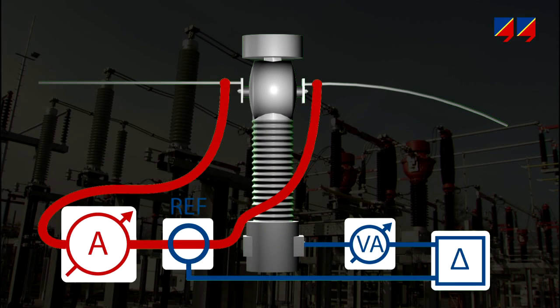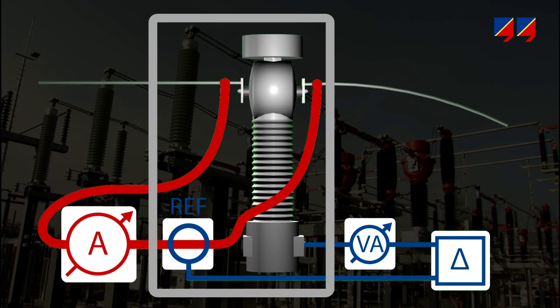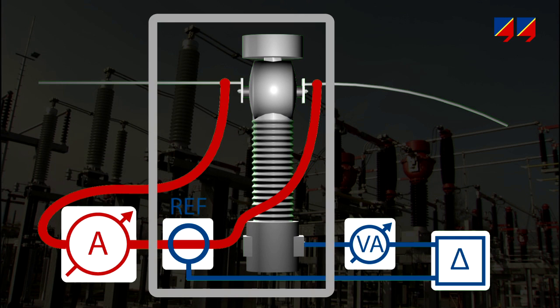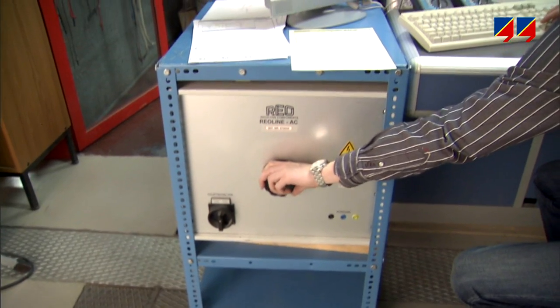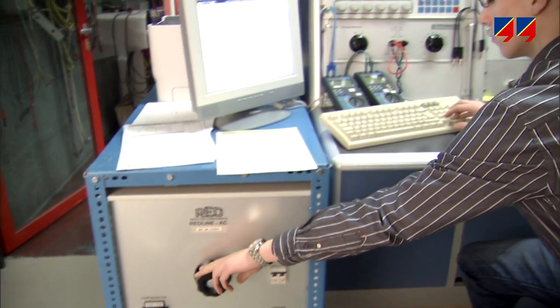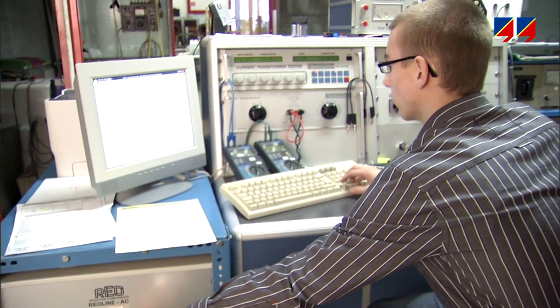If a CT is to be comprehensively tested in a classical manner, the current bridge method is used. Through a high current source, defined values of primary currents — from fractions to multiples of rated current — are injected into a reference CT and the CT under test, which is connected to a controllable burden box to simulate different load conditions. Via a measurement bridge, the output currents from both CTs are compared in amplitude and phase. With this method, all current and burden value combinations defined by the relevant international standards can be verified and the CT's compliance can be assessed.